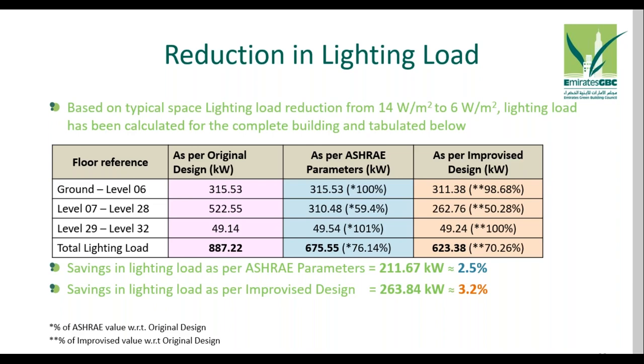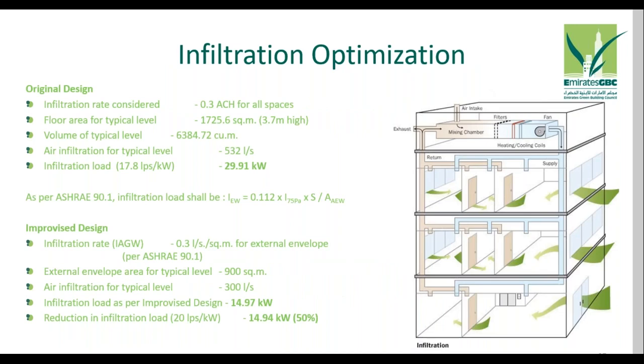So we discussed occupancy, we discussed fresh air, we discussed lighting. The next parameter we considered was infiltration. When we talk about infiltration, as we know, it depends on two parameters. One is the external and internal pressures. Second is the stack effect, which changes during winter and summer seasons. But predominantly, infiltration is applied to the facade of a building. By and large, infiltration is applied based on air changes. So we have huge floor plates and we apply air changes of say 0.1, 0.2 or 0.3.